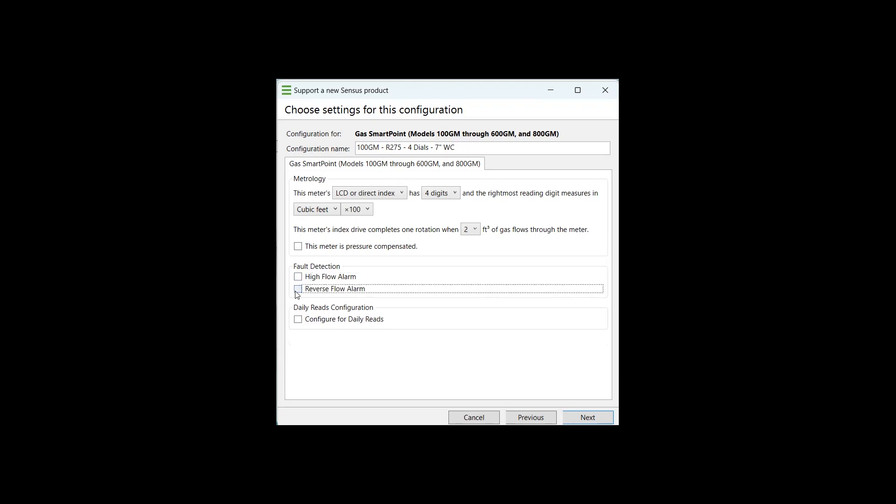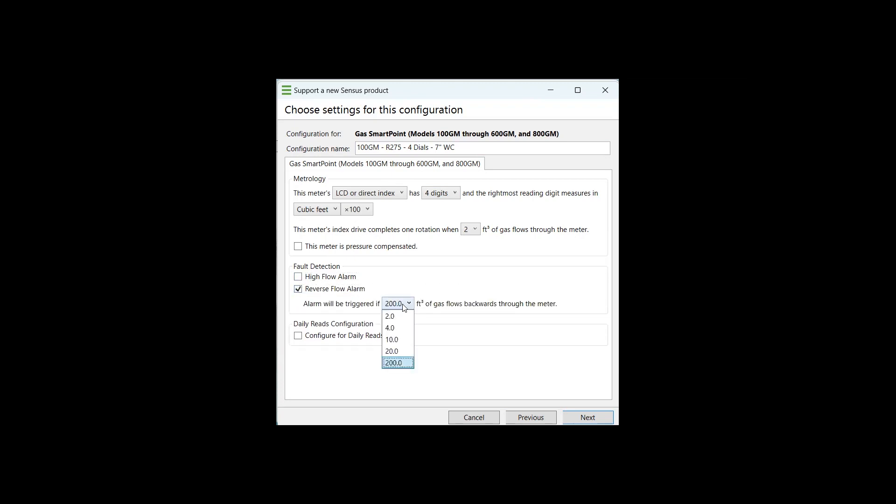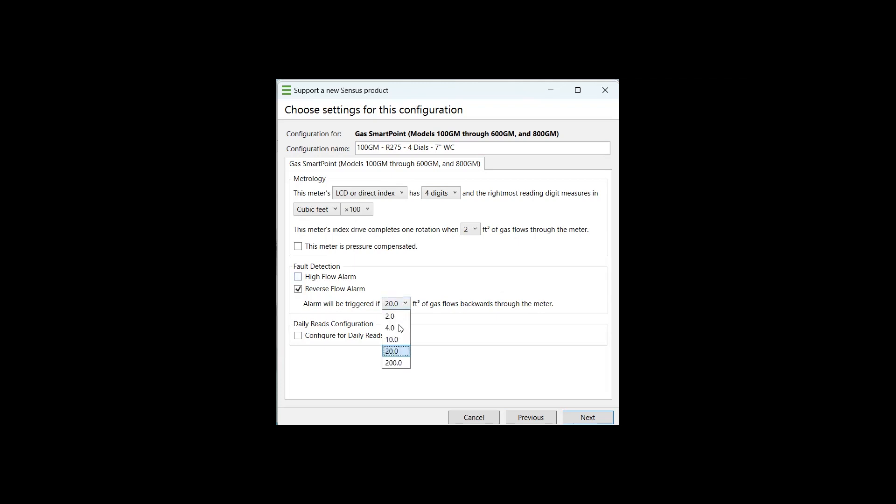I do recommend the reverse flow alarm personally, because essentially this is going to indicate whether or not a customer has removed that meter from service, flipped it around and tried to run that meter backwards. So the alarm will be triggered. I typically like to put at least 20 cubic feet of gas flowing backwards through that meter. Every natural gas setting is going to have some fluctuation. So you want to make sure it's at least above 10 for that setting, in our personal opinion.